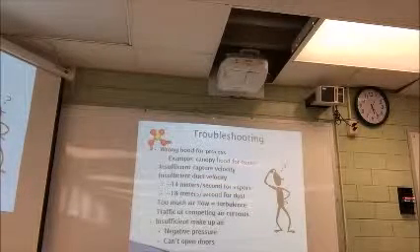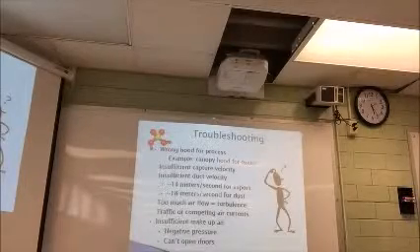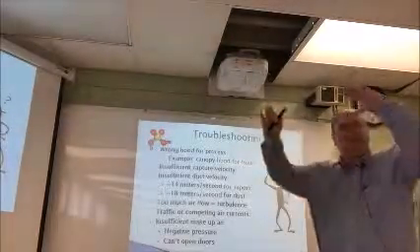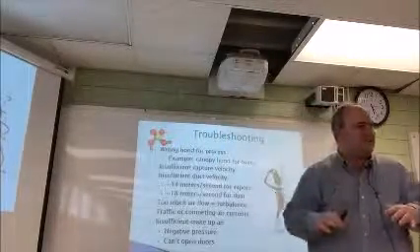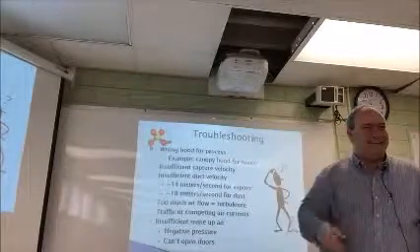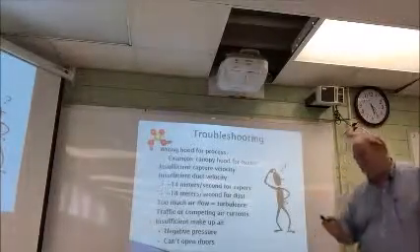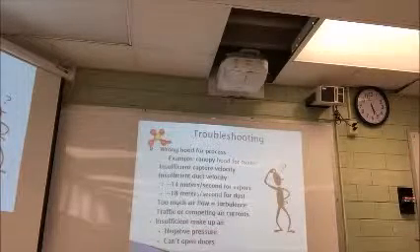You guys know that. If you're trying to use a canopy hood, and the canopy hood's above it, what do the vapors have to do? If they're heavier than air, what's going to happen? Yeah, it's never going to work, is it? You're probably not going to be able to use it. So that's kind of areas.